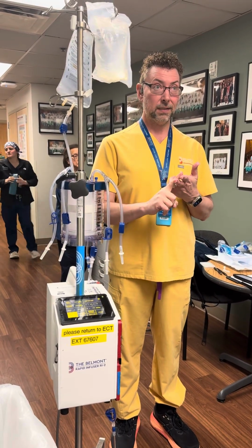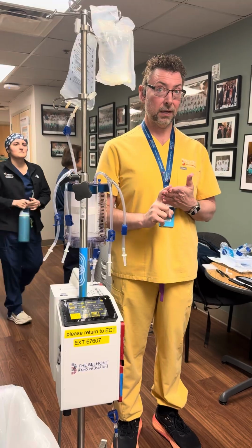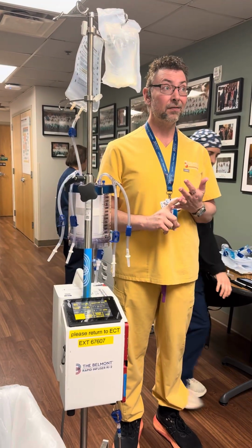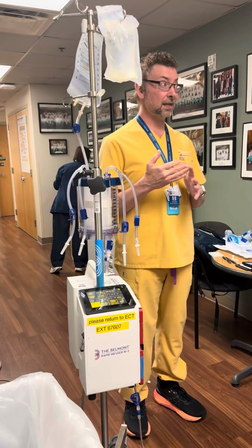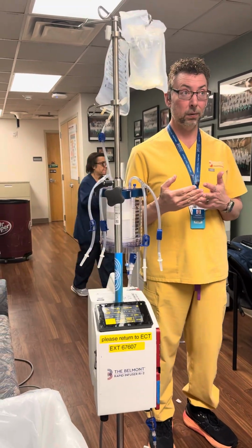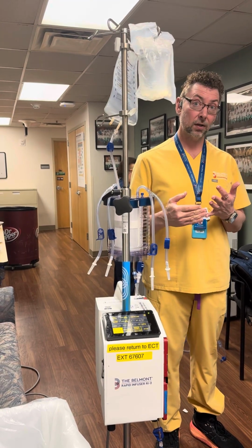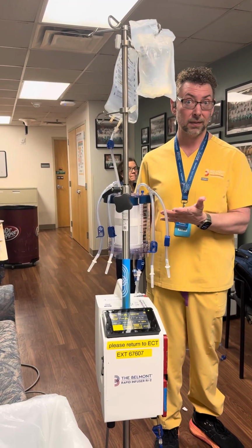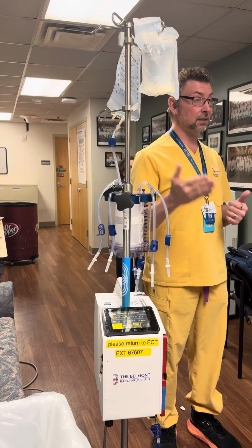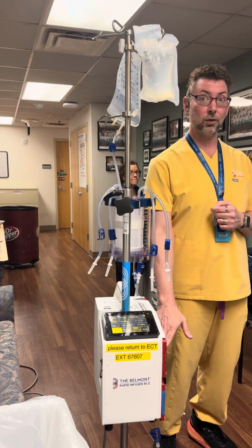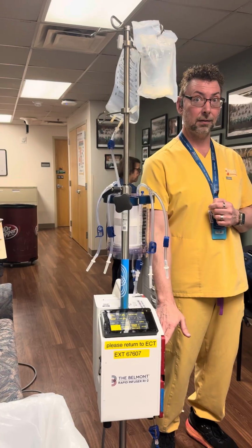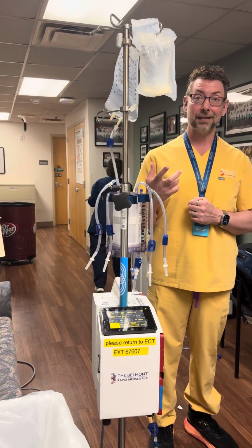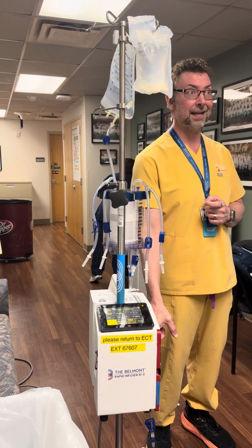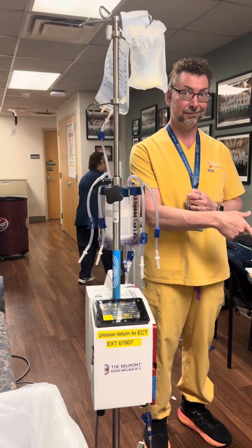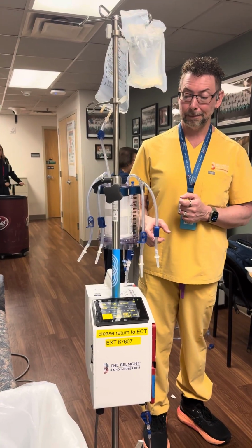Platelets, cryoprecipitates, lactated Ringer's in combination with blood, albumin if it's above 5%. So PRBCs, FFP, anticoagulated whole blood, heparinized cell salvage blood, and albumin, as long as it's not above 5%, is all safe to go through the system. Above 5%, you turn your albumin into scrambled eggs when it goes through our heater. And platelets and cryo, you run your risk of starting the clotting cascade in our heater versus in your patient.